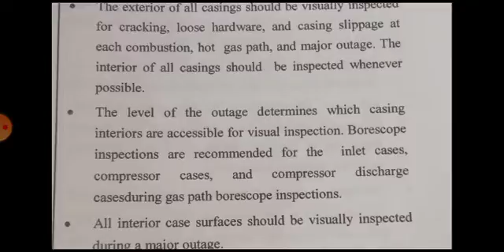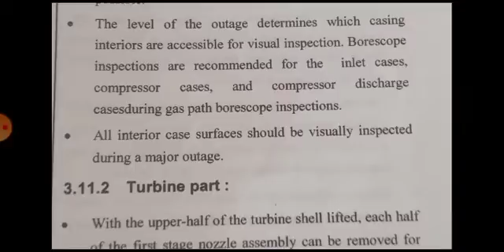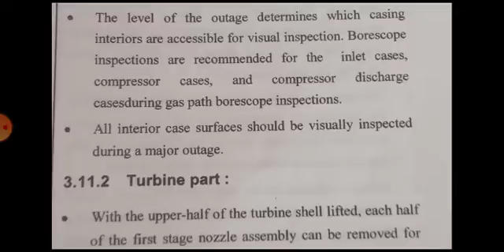The interior of all casings should be inspected whenever possible. The level of the outage determines which casing interiors are accessible for visual inspection. Borescope inspection is recommended for the inlet cases, compressor cases, and compressor discharge cases during gas path borescope inspection. All interior case surfaces should be visually inspected during a major outage.